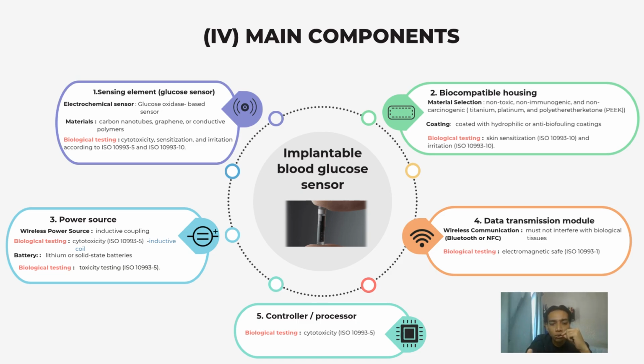And then the next component is the power source. There are two types of power source. The first one is wireless power and then battery. The wireless power source type usually uses the concept of inductive coupling. This type of power source must undergo biological testing of cytotoxicity based on ISO 10993-5, specialized for the inductive coil. And for the battery, we usually use lithium or solid state batteries. The biological testing that must be done on this type of power source is toxicity testing based on ISO 10993-5.